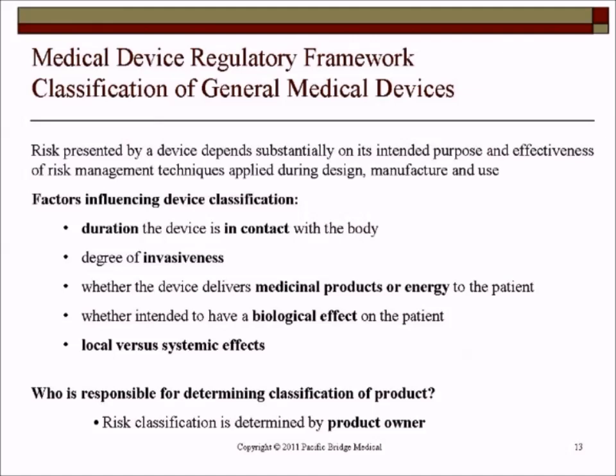Moving to classification of general medical devices: anyone familiar with the medical device directive in the EU will find this rather familiar, as most regulations are based on the GHTF regulations, and classification in turn is based on the MDD directive. So the key thing to note is that if you have already classified this device under the MDD directive, you are likely not required to perform another reclassification in Singapore.